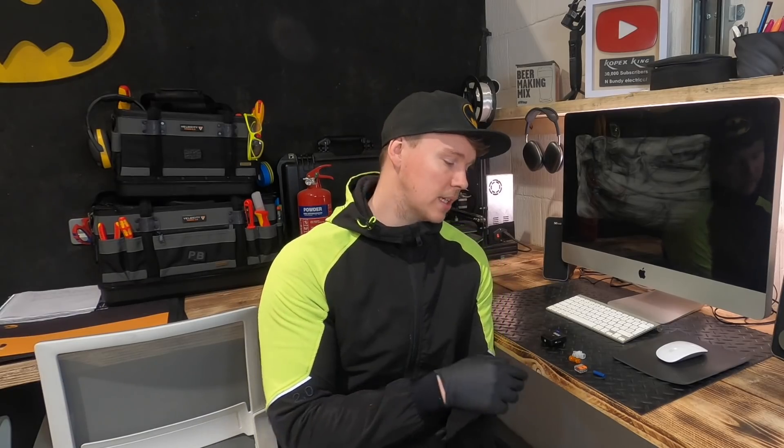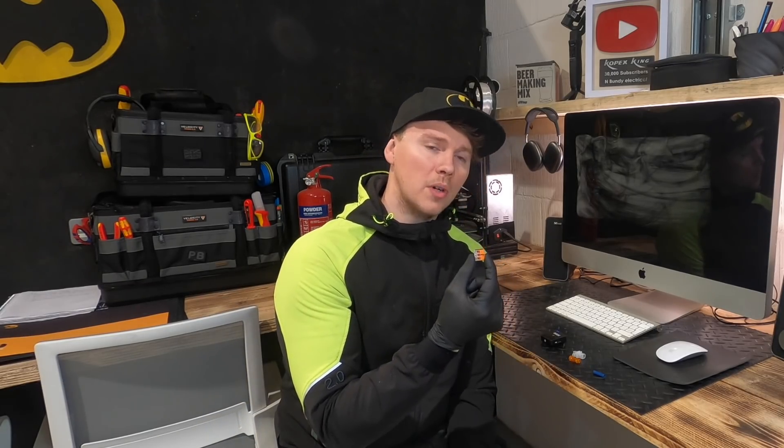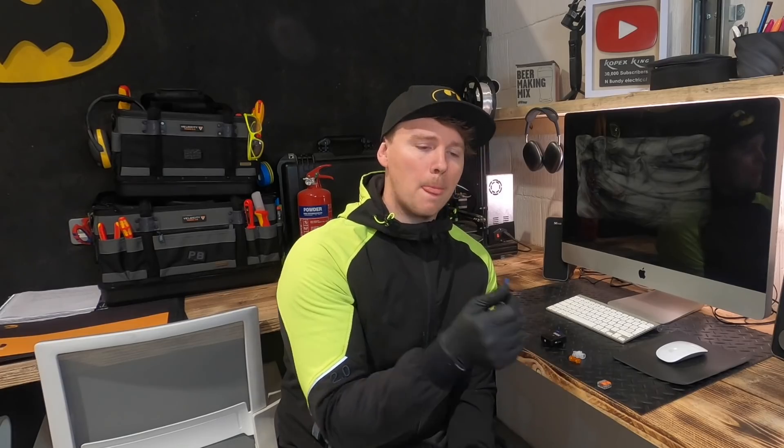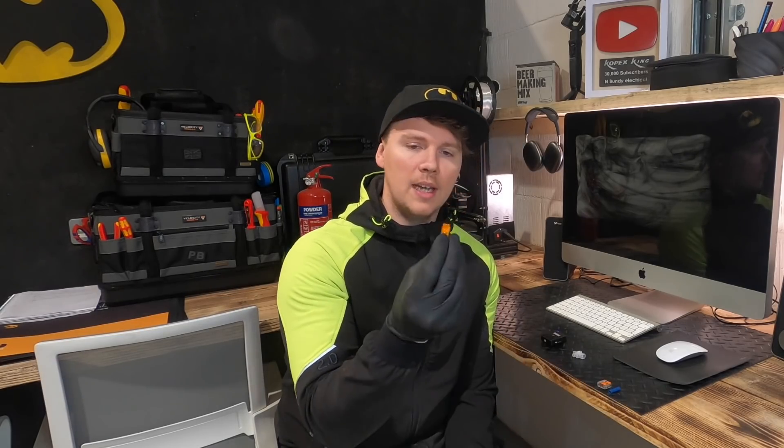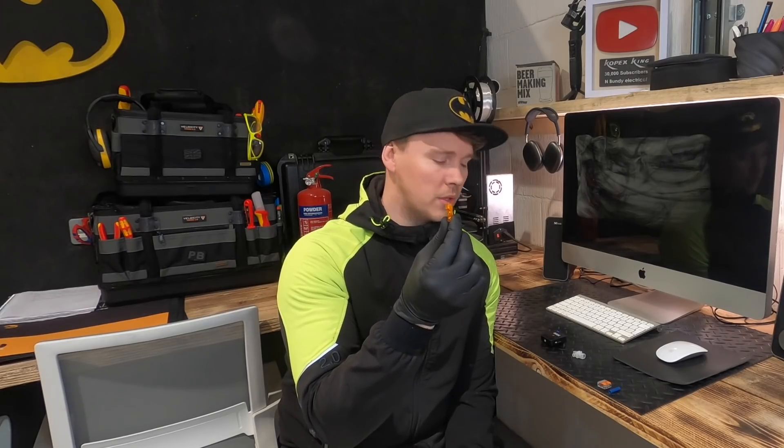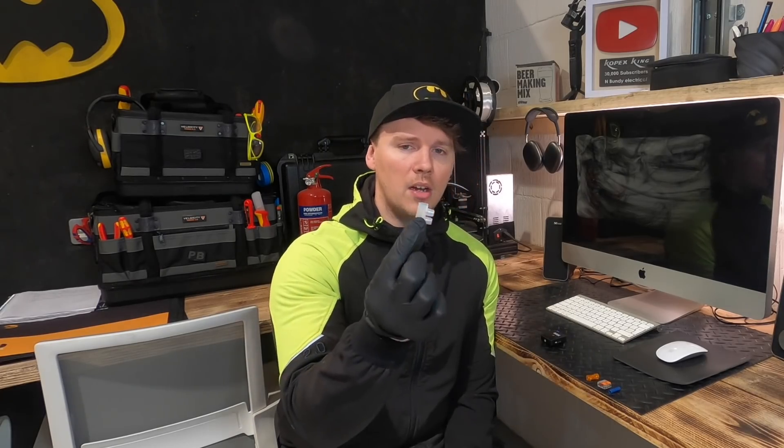So today I have brought a welder. With the welder, it goes from 10 amps to 160. I'm going to be pumping as much amperage as I can through different connectors. So this video will be about the different types of connectors. We've got a Wago 221, which is rated 20 amp. We've got a Unicrimp through crimp, which is rated 20 amp. We've got an Ideal splice line, which is rated 32. And our one and only connector block, which is rated 30 amp.